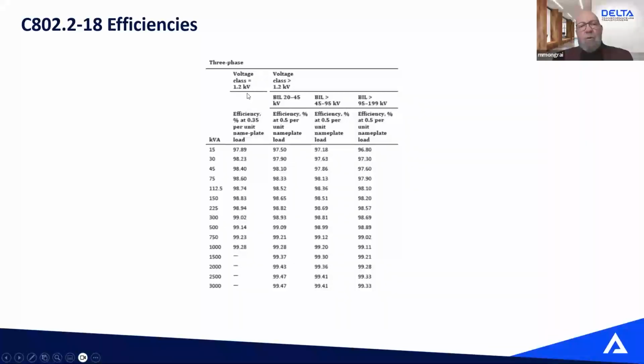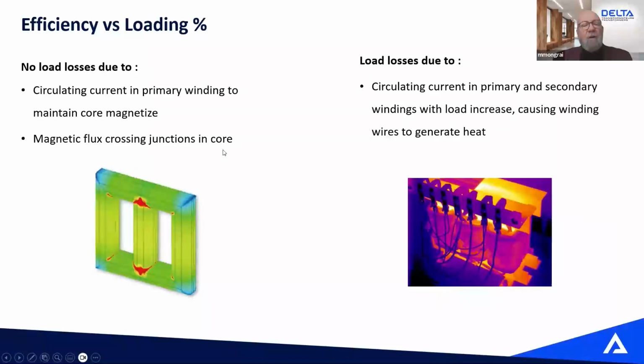But the trick is, for low voltage class, 1.2 kV and less, we have to meet this efficiency level at 35% load, and for any voltage class above 1.2 kV, we need to meet this efficiency requirement at 50% load. So that efficiency curve from different manufacturers can be quite different depending on your transformer construction. Just by saying, yeah, I'm efficient as per CSA, it means that at 35% load you meet this point, but at 75% load, what's your efficiency, Mr. Manufacturer? There can be lots of difference between manufacturers in that regard.